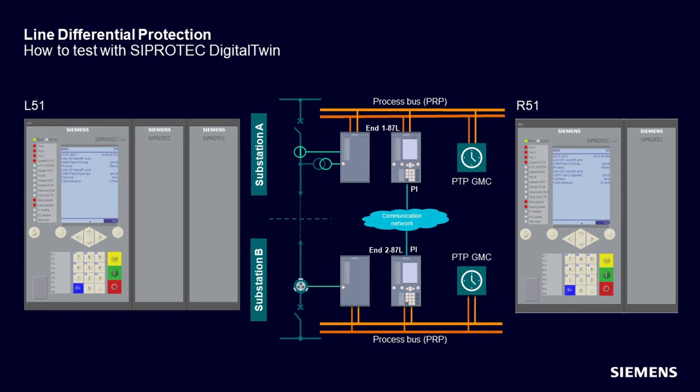From that perspective, we are testing in the same way if we have line differential protection for conventional applications, for process bus applications, or for mixed applications. That is where one end uses process bus technology and the other end conventional implementation.